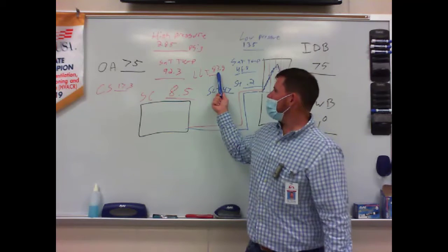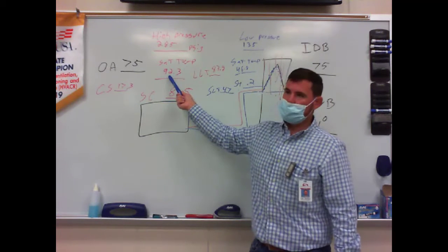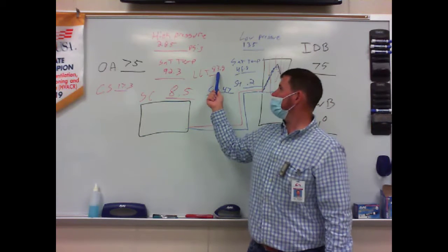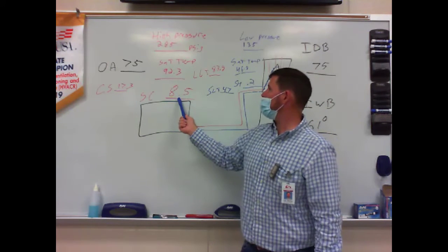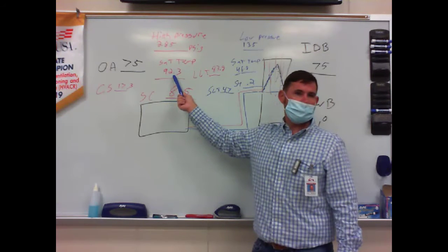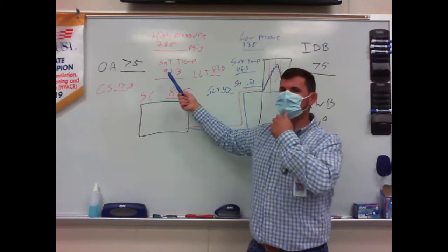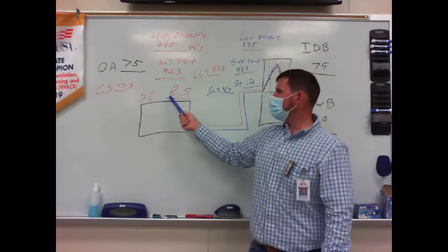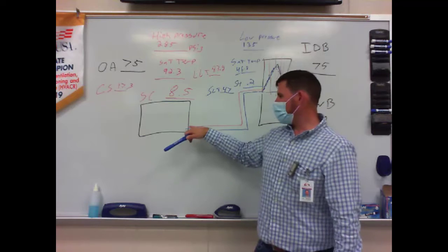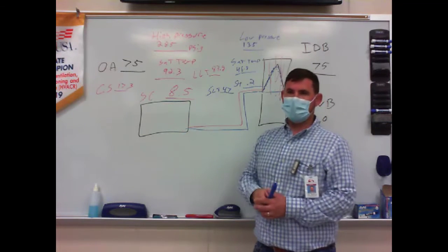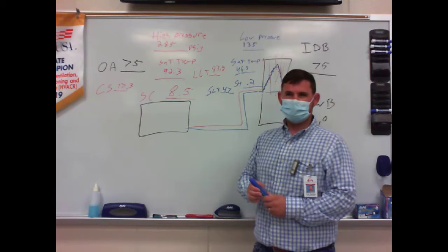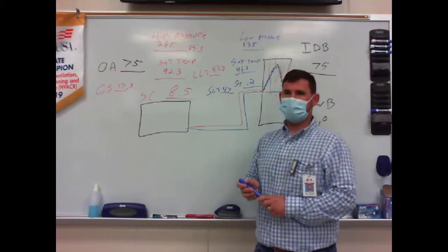Is 83.8 cooler than 92.3? Yeah, 83.8 is 8.5 degrees colder than 92.3, right? So I turned into all liquid and I cooled it an additional 8.5 degrees. So I know that I have all liquid coming out of there because I am subcooled. Does that make sense, Kyle?